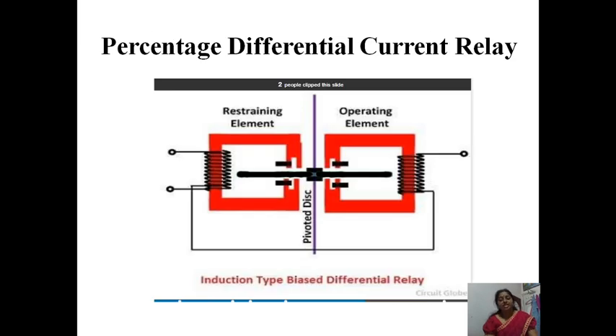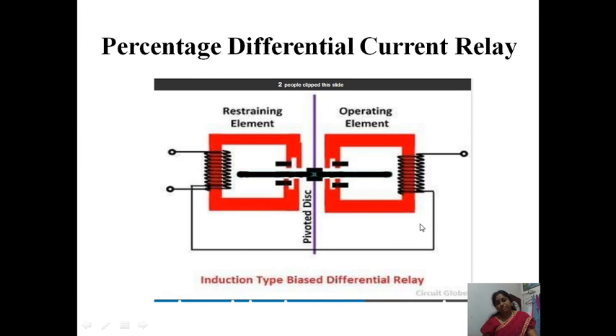In percentage differential protection, we have an operating coil or operating magnet and a restraining element. This restraining coil is divided into two halves. Here, an induction type bias differential relay is shown. You can see the restraining element and the operating element. If you consider the first terminal, second terminal, and third terminal — between the first and second, the coil is connected and given to the operating element. These windings on each side are equal.